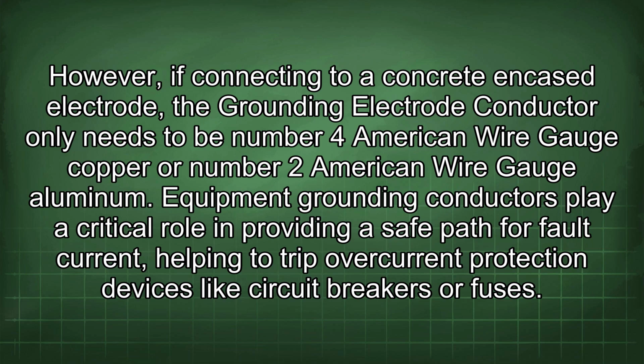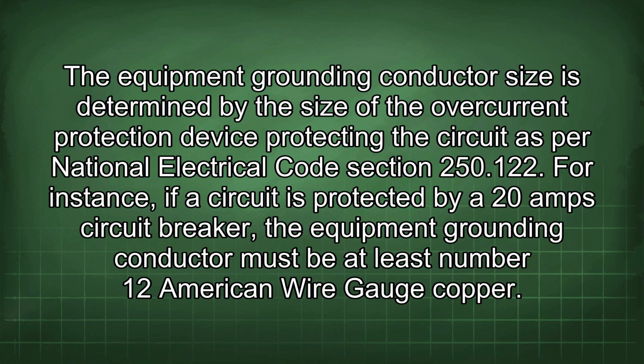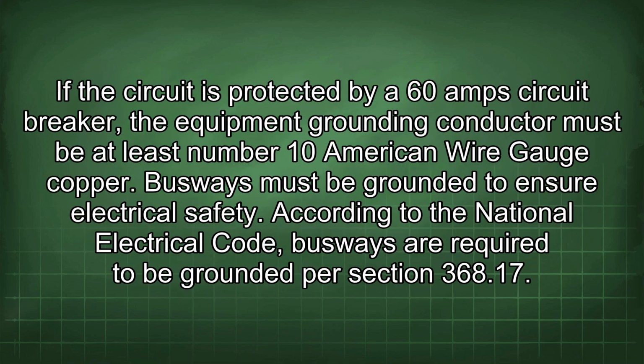Equipment grounding conductors play a critical role in providing a safe path for fault current, helping to trip overcurrent protection devices like circuit breakers or fuses. The equipment grounding conductor size is determined by the size of the overcurrent protection device protecting the circuit as per National Electrical Code section 250.122. For instance, if a circuit is protected by a 20 amp circuit breaker, the equipment grounding conductor must be at least number 12 American wire gauge copper. If the circuit is protected by a 60 amp circuit breaker, the equipment grounding conductor must be at least number 10 American wire gauge copper.